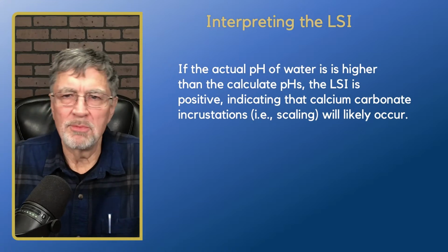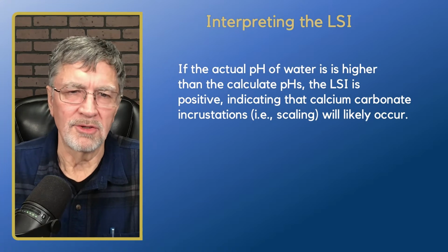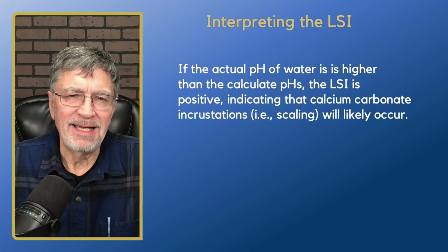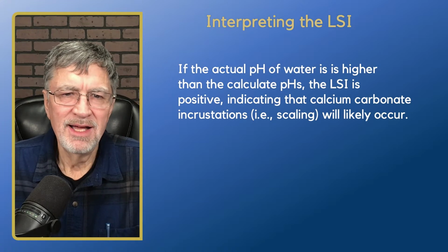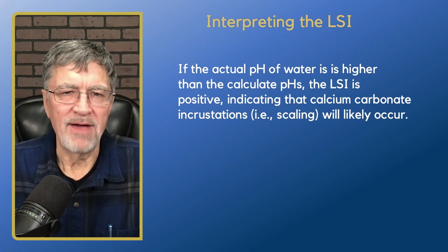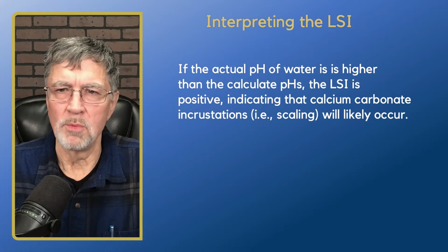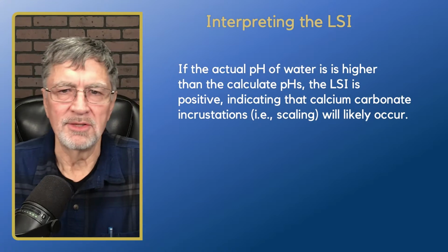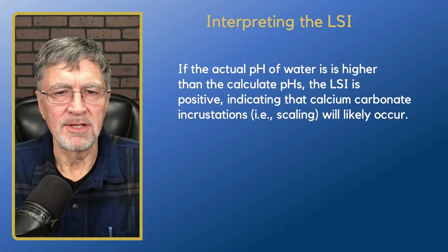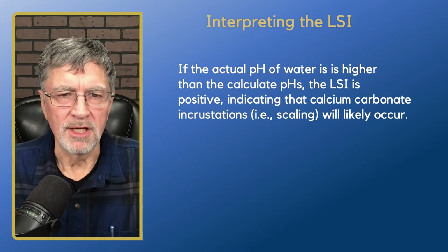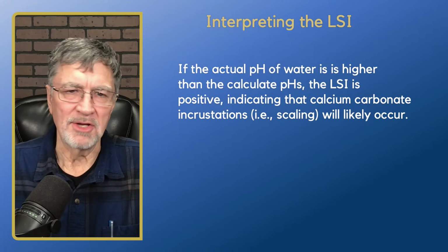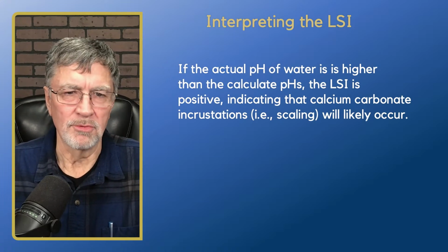And so basically interpreting the LSI, now some people will tell you that LSI will tell you the corrosivity of the water, and that's based on the fact that as water becomes more acidic or the LSI decreases, you are looking at removing a protective coating of calcium carbonate in the well, and that makes it more likely to corrode.